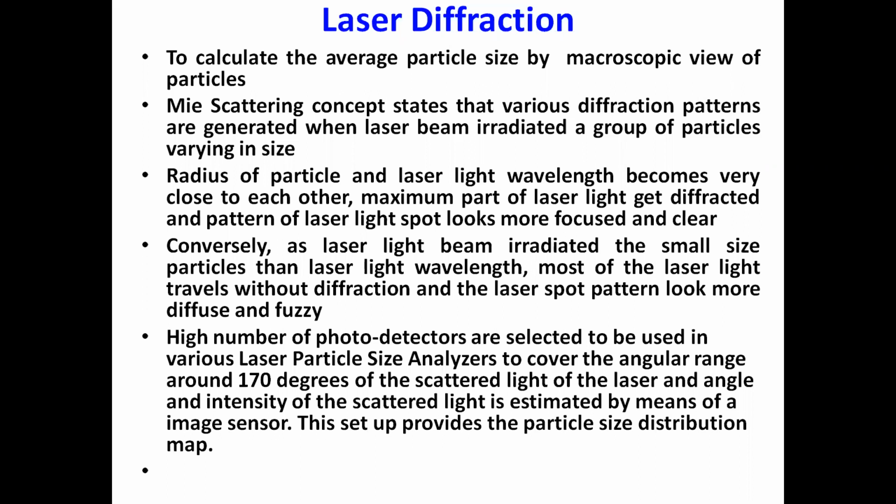A high number of photodetectors are used in various laser particle size analyzers to cover the angular range. Meaning, when light is dispersed in different directions, we have to put different numbers of detectors to capture all the images of all particles.